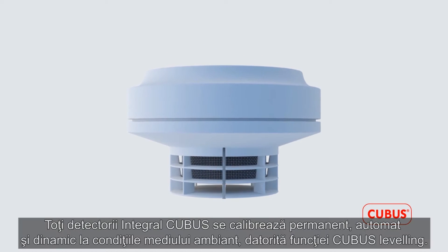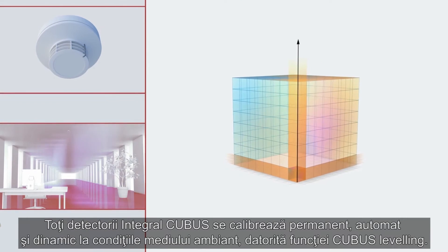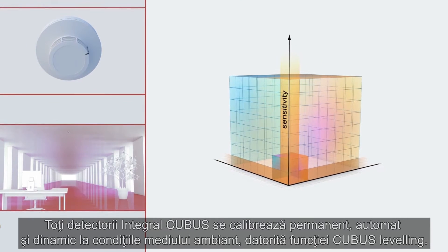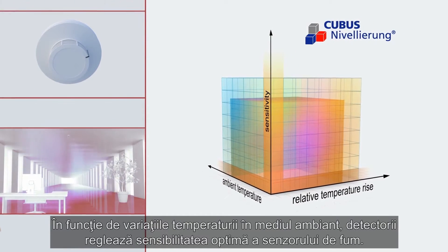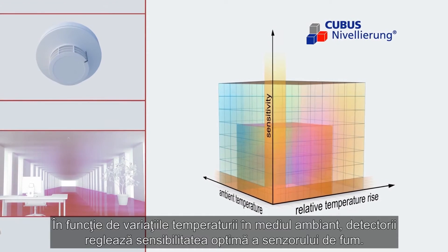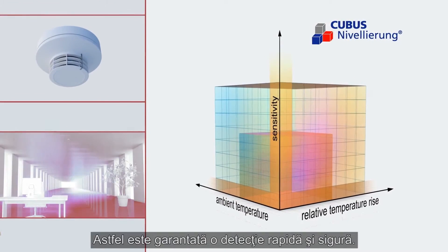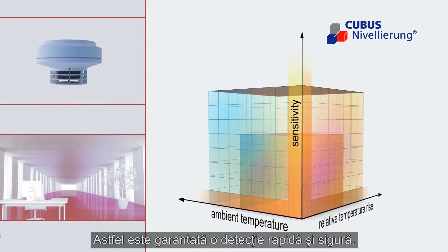All fire detectors in the Integral CUBUS series automatically adjust their sensitivity in accordance with the surrounding environmental conditions using the unique CUBUS levelling process. Depending on how the ambient temperature changes, the fire detectors then set the optimum sensitivity of the smoke sensor, consequently guaranteeing quick and safe detection.